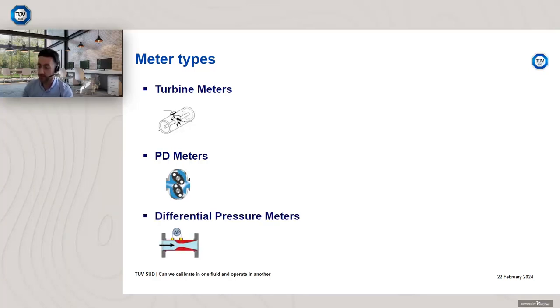Differential pressure meters. Now this is one such device that isn't so much fluid independent, but can be calibrated with one fluid, be it water or oil, and then used in gas, or calibrated in gas and then used with a liquid. So there certainly are various applications, and certainly we often calibrate flow meters for gas and water by matching Reynolds number.